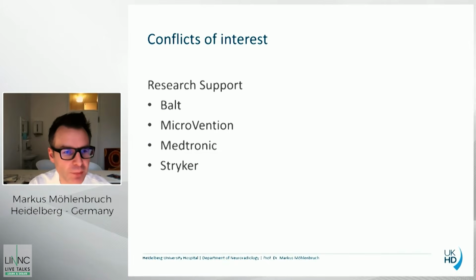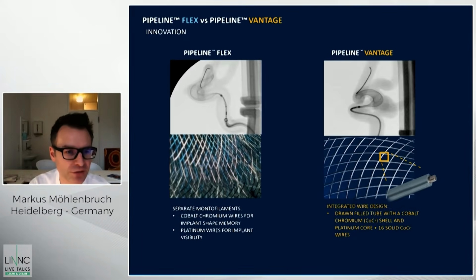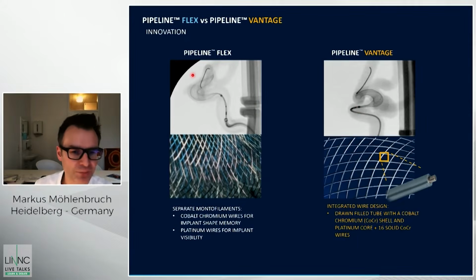When we discuss the Pipeline Vantage, here you see a direct comparison to the Pipeline Flex. As you probably all know, the Flex consists of cobalt chromium wires for the implant shape memory and platinum wires for the implant visibility. Whereas the Pipeline Vantage, which is a completely new design flow diverter, is composed of DFT wires with a cobalt chromium shell and a platinum core, and 16 solid cobalt chromium wires. If you look at the pictures, you see that the visibility of the Vantage is much better, much clearer compared to the Pipeline Flex.